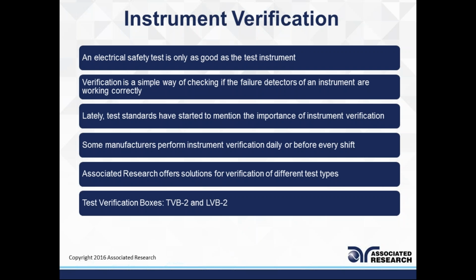An electrical safety test is only as good as the test instrument itself. If the test instrument is not functioning properly, then any test or any product tested using that piece of equipment will not be a valid test. It can result in false passes, and may pass products that were not supposed to pass, that were faulty, had some kind of issue, or could be a source of injury to the end user, but they got passed because the instrument was not verified for proper functionality.